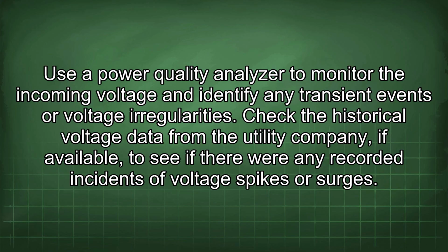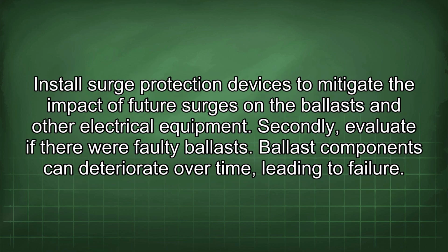Check the historical voltage data from the utility company, if available, to see if there were any recorded incidents of voltage spikes or surges. Install surge protection devices to mitigate the impact of future surges on the ballasts and other electrical equipment. Secondly, evaluate if there were faulty ballasts.